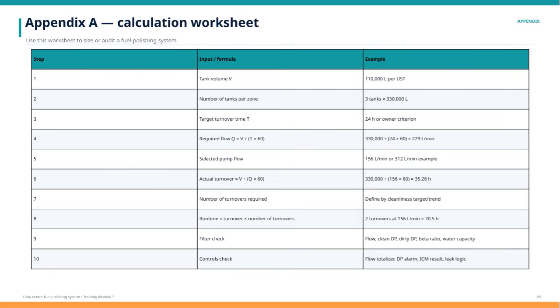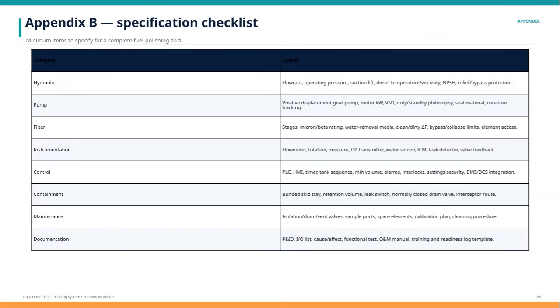to maintain fuel integrity. Here we have Appendix B, which serves as a specification checklist for a complete fuel polishing skid. This checklist ensures that all critical components and parameters are properly defined for optimal system performance. Starting with the hydraulic category, it is essential to specify flow rate, operating pressure, suction lift, diesel temperature and viscosity, net positive suction head, and relief or bypass protection. These factors directly impact the hydraulic performance and reliability of the system.